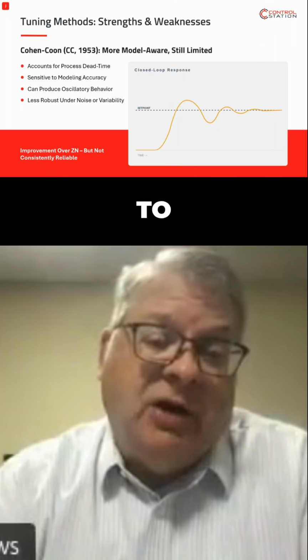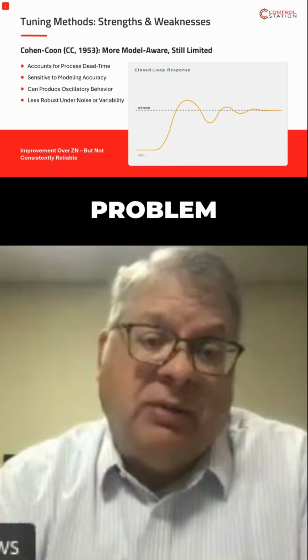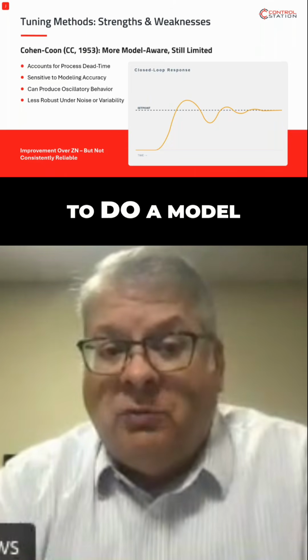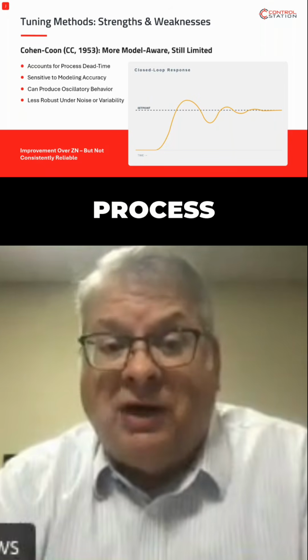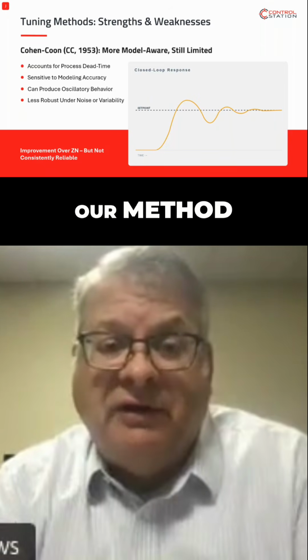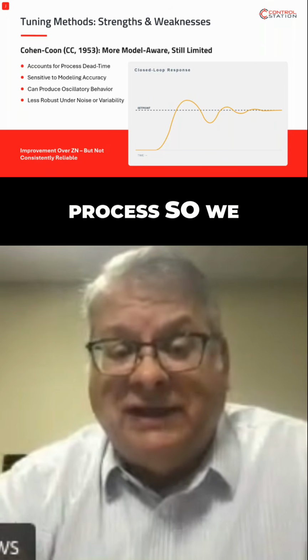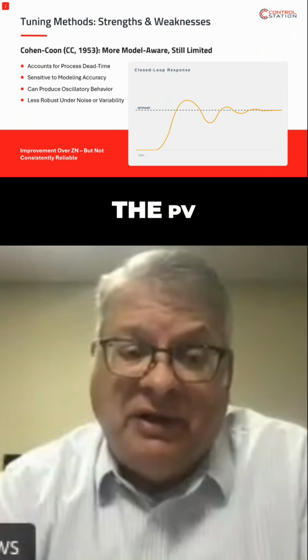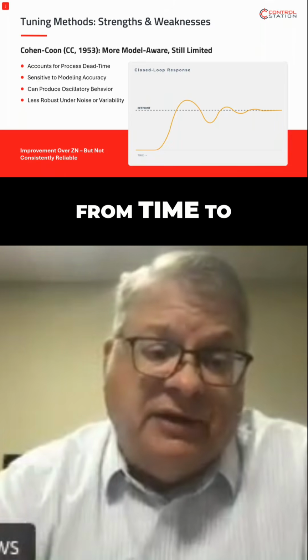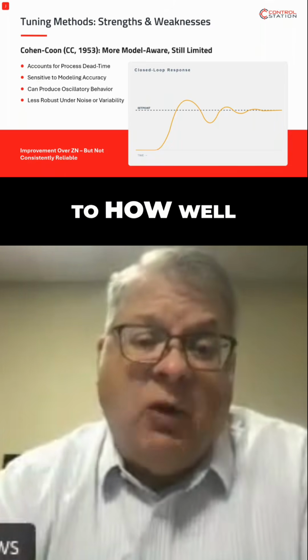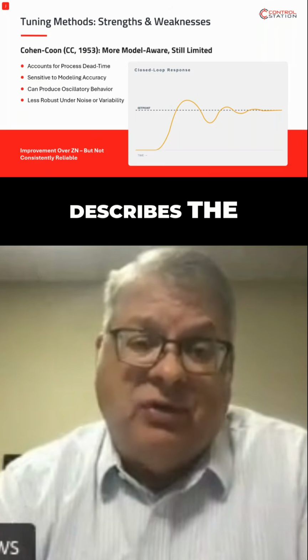It is sensitive to model accuracy, and there's a problem. So whenever you go to do a model in a process, you'll bump your process. You'll hear us talk about that in our method, is to bump the process so we can see a response between the control output and the PV. So you'll see that from time to time. And it's very sensitive to how well that model describes the process.